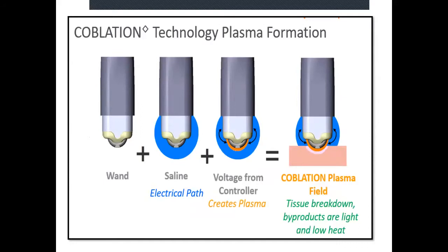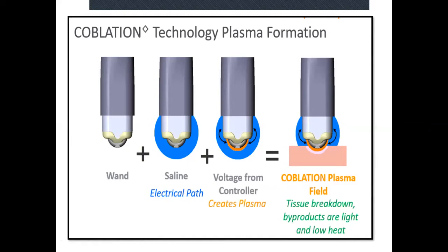This describes the same process: the electric path voltage from the controller — the console and the generator — creates the plasma field wherein tissue breakdown produces light and low heat. Once that energy is generated at the tip of the wand, the plasma actually breaks the covalent bonds between protein molecules — that's how coblation is executed.